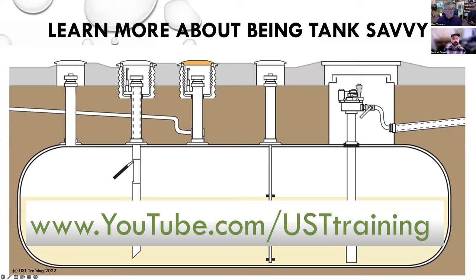And then a couple other folks have raised some points in regard to what we were talking about previously. Ellen Mank says CSLD can be used for manifold tanks without closing siphon, but I believe there's a total capacity limit listed on NWGLDE. Correct. Yeah, thank you, Ellen. I thought that was the case. So if the total capacity of both tanks is under 30,000 gallons, I think you're okay. But if you've got two giant monster 20, 25, 30,000 gallon tanks, it may exceed that.